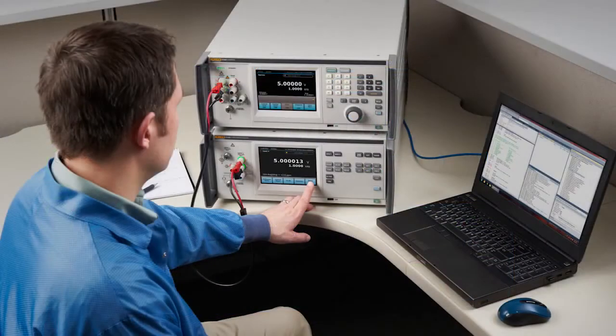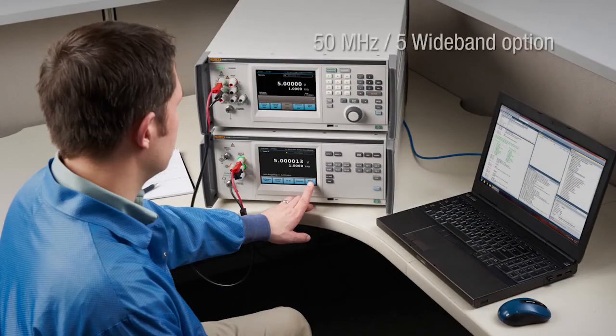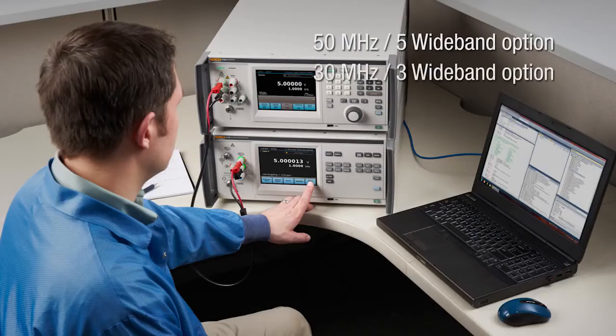The fourth major improvement is the addition of the 50MHz wideband option that extends the bandwidth to 10Hz to 50MHz for calibrating precise RF power sources. Like the 5790A, the 5790B still offers a 30MHz wideband option ranging from 2.2mV to 7V and with a frequency range of 10Hz to 30MHz.